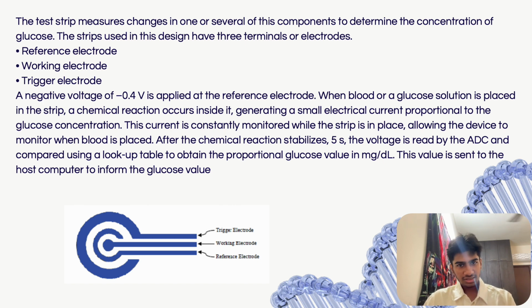The strips used in this design have mainly three terminals or electrodes, as shown here. There is a trigger electrode, a working electrode, and a reference electrode. Now, a negative voltage of minus 0.4 volt is applied at the reference electrode. When a blood or glucose solution is placed in the strip, a chemical reaction occurs inside it. This generates a small electrical current which is proportional to the glucose concentration. This current is constantly monitored using a device in which the strip is placed.